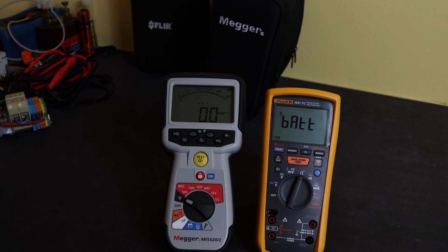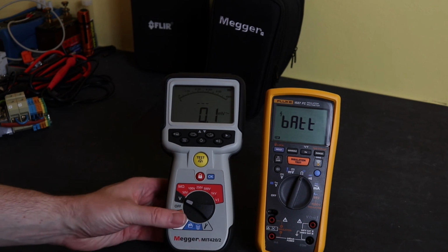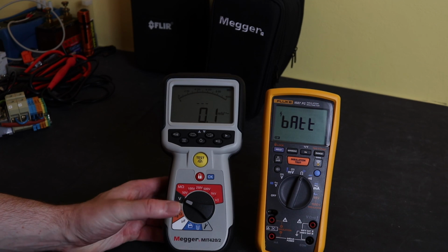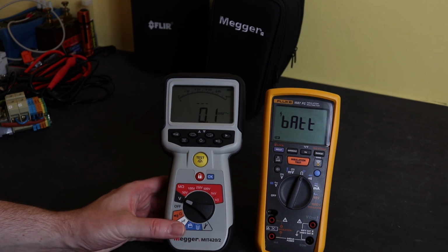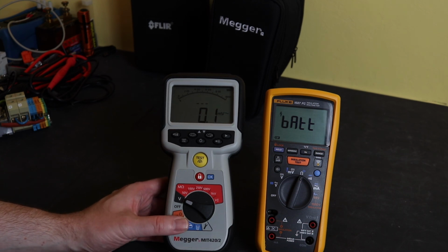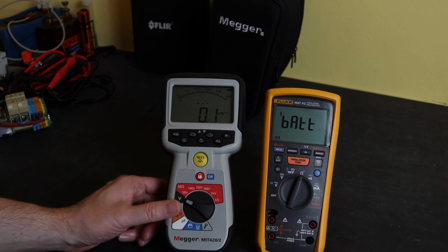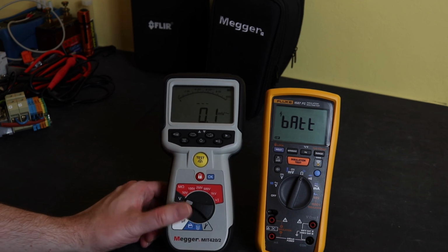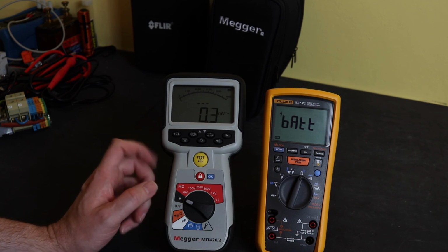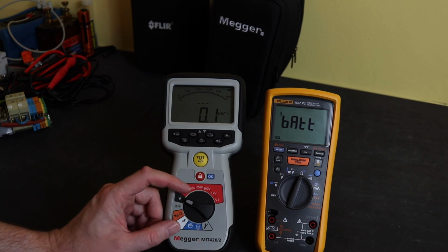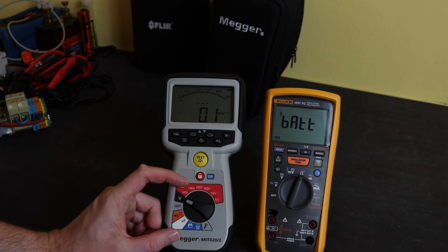Yeah, and that's pretty much it for the comparison of those two instruments. In terms of which one I would go for, as with a lot of these things, because they're such different instruments, it depends exactly what you want from your testing. Generally speaking, I go for the Megger. I'm much more into insulation resistance testing on motors and the ability to actually record a reading and then trend that reading over a period of time. Since most of my testing is done at 500 volts, I can usually get good DAR and good PI readings from that test at that voltage and record them for future trending.